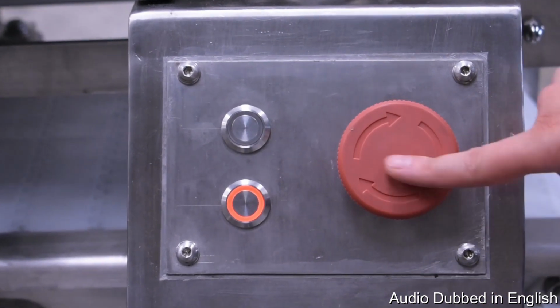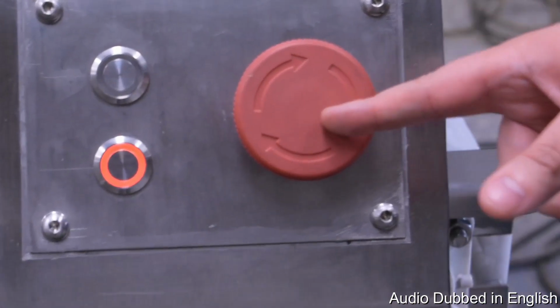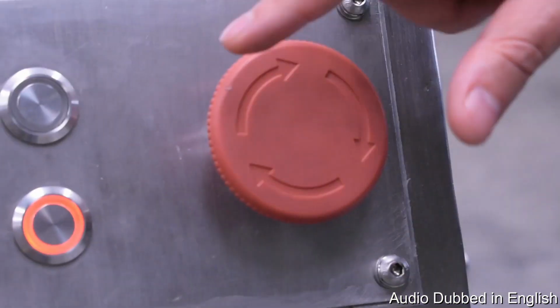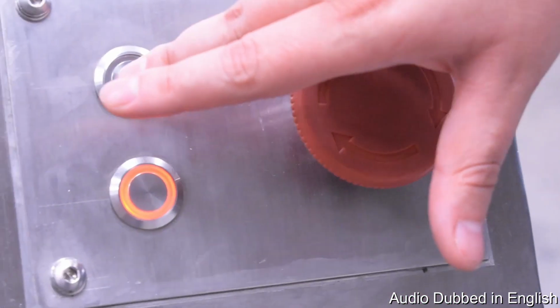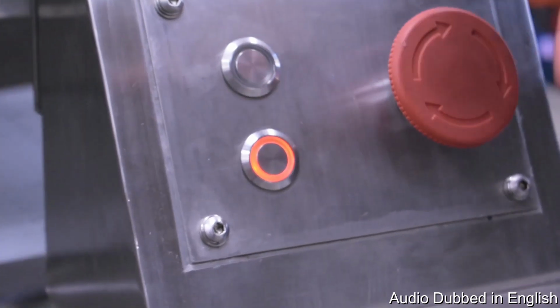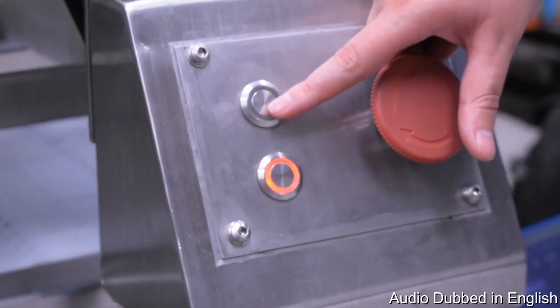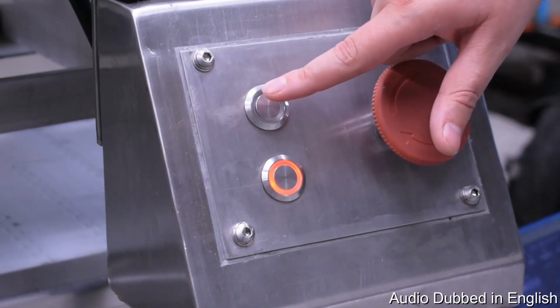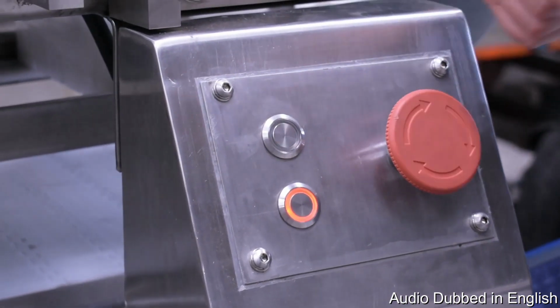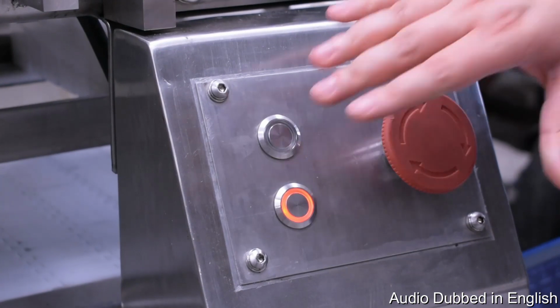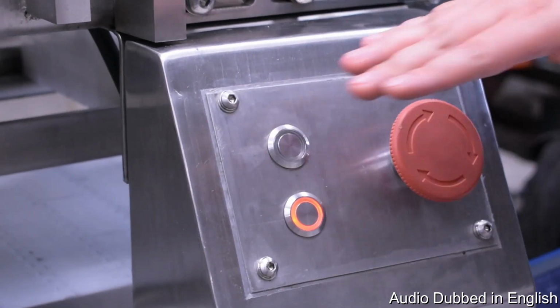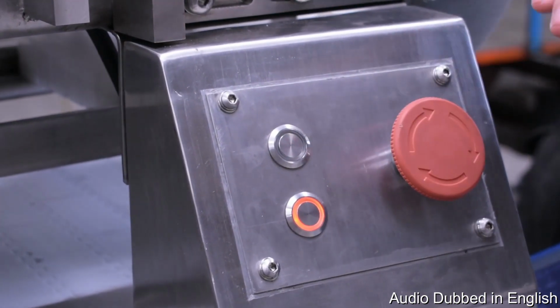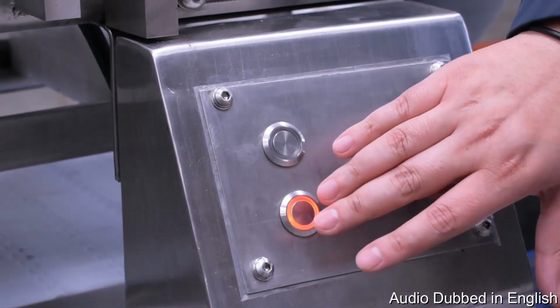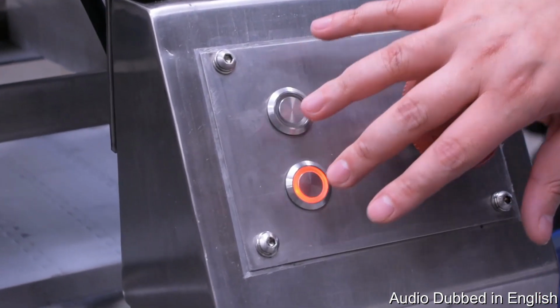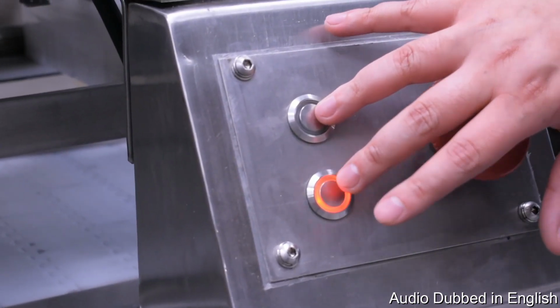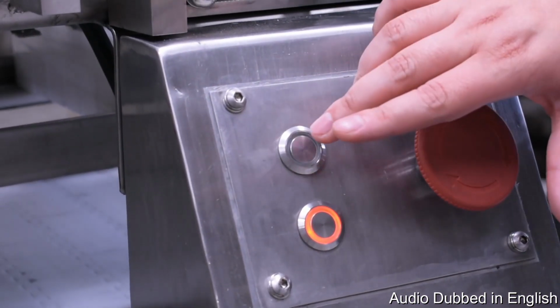So the first thing we're going to do is detach our mushroom emergency stop button. And then we're going to start our system, but I'd like you guys to notice something very important, something that we had already seen in the course. Only by pressing once, it should latch. I should not leave it pressed or else it's going to be a jog. I don't need a jog. It's a regular startup. And with this other button, we can stop all of the system. Okay, here we go. 3, 2, 1, go.